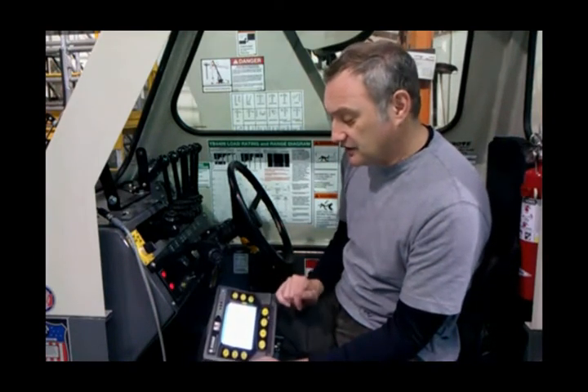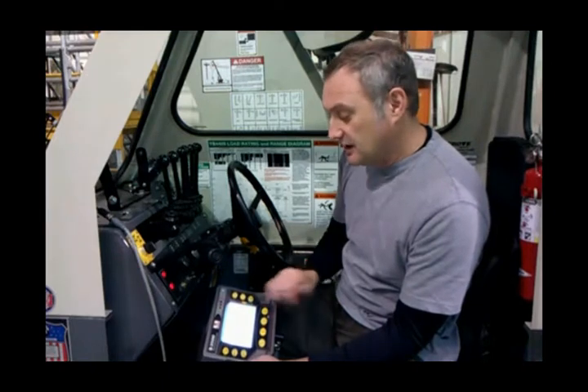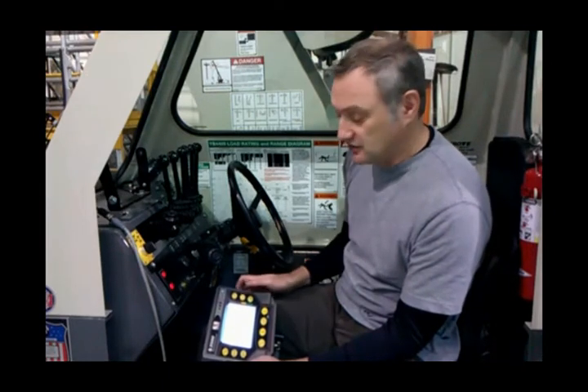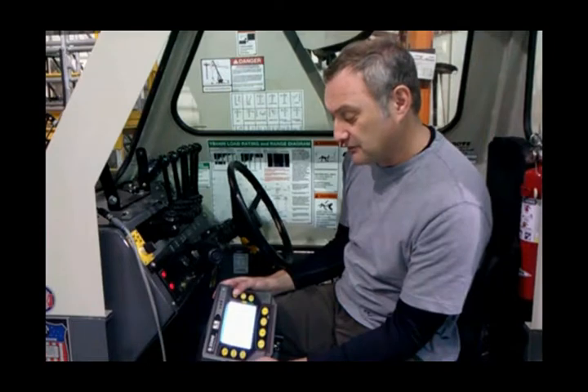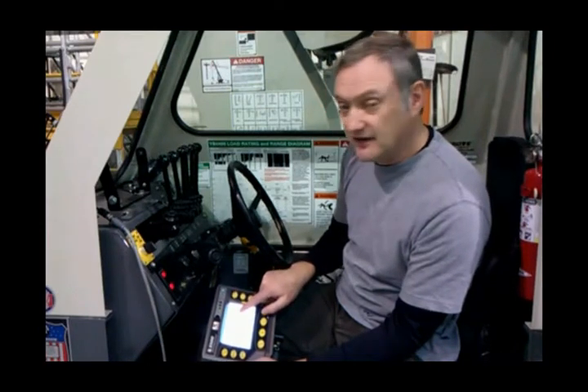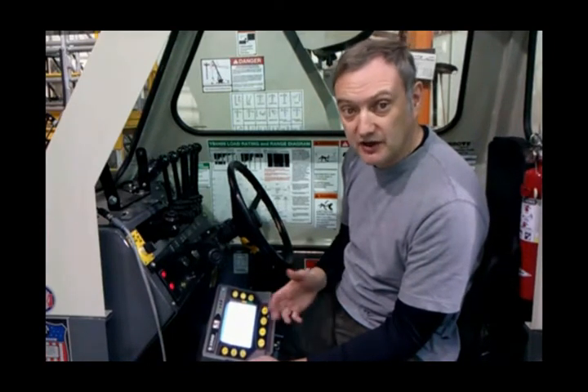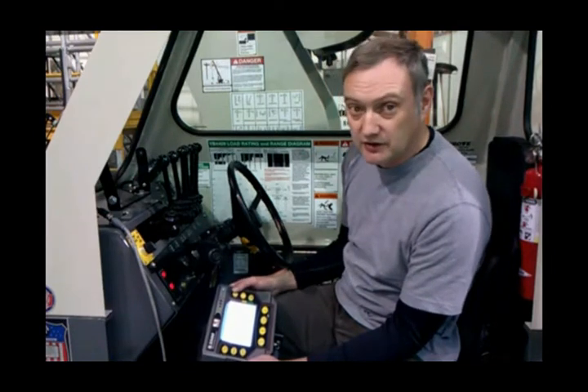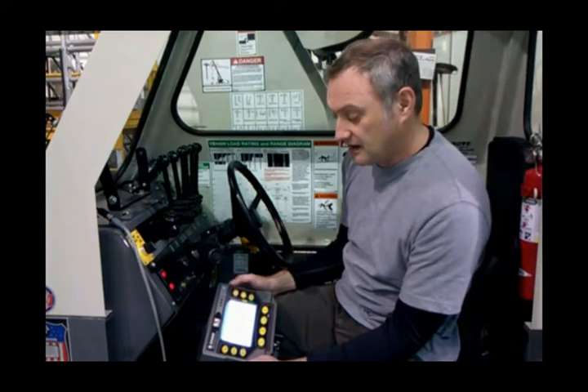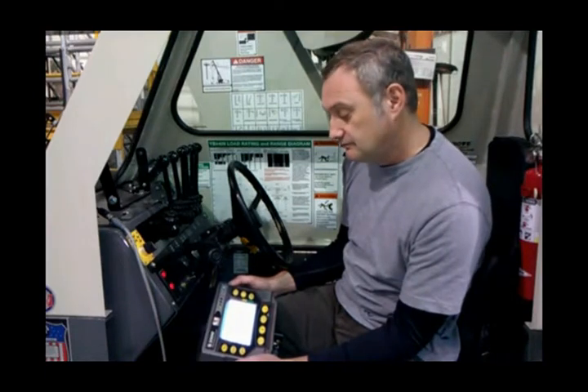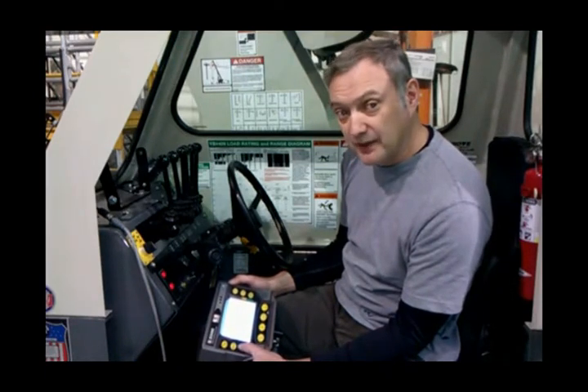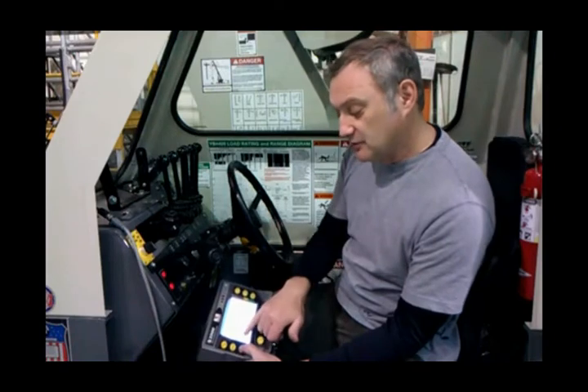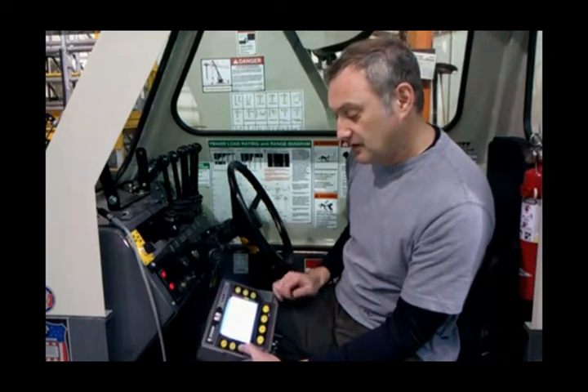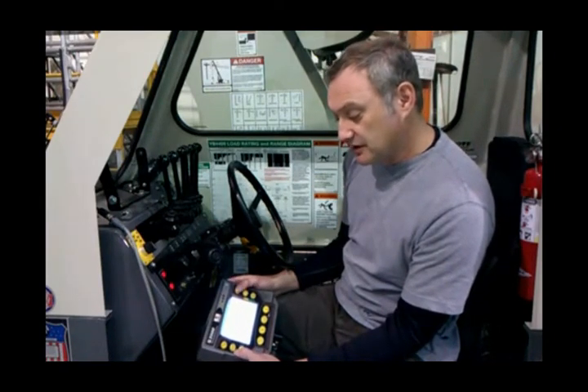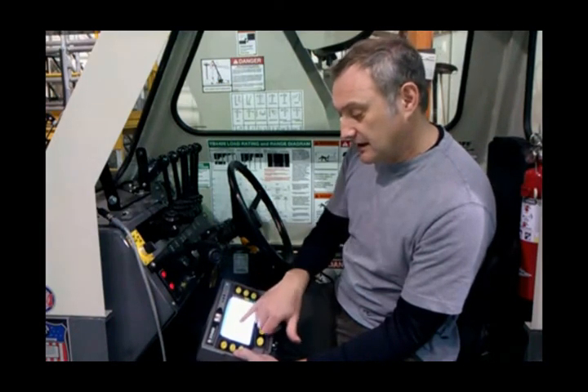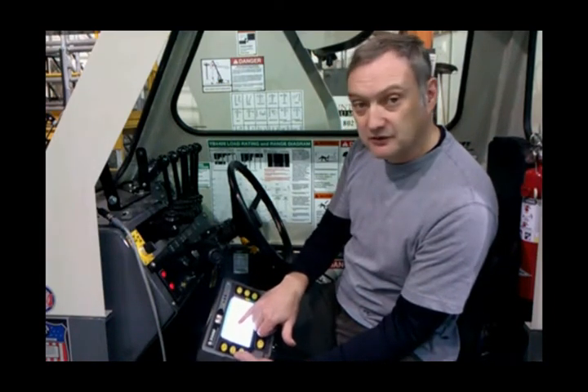So right now, we've got a good value here of 305, and our negative 2.2 needs to be changed. So what we're going to do is hit button number 4, and it's going to highlight that box where the negative 2.2 was and go to 0, which is what we want it to do. So we're going to hit the check mark again, and it's going to save the value. The next thing we're going to do is span the sensor, which is item number 6, span pressure. So we drop down, we hit the check mark to select it, and it's telling us that we're looking at a span for load 1.